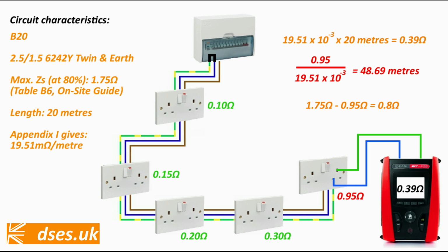Obviously, a loose connection on R2 could be throwing both results out, but you perhaps only need to worry about that if both results seem high, as R2 isn't likely to trouble an AFDD. It's there for fault current, and any such current ought to trip the breaker or RCD in short order. Still, for the sake of it, if both R1 plus R2 and Rn plus R2 are giving us a high reading that seems unlikely considering circuit length, 0.95 ohm here indicating a circuit length of 49 metres, then we could measure R1 plus Rn.